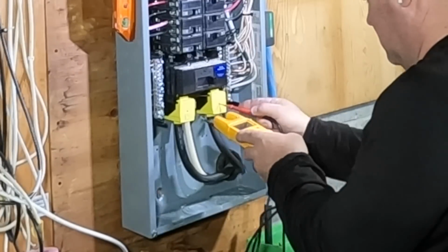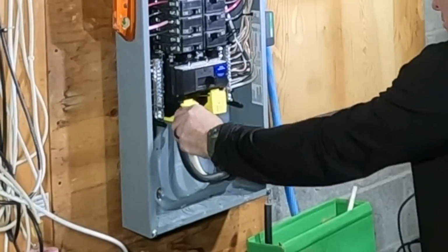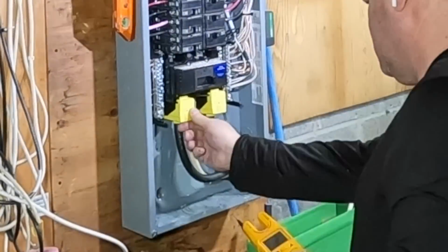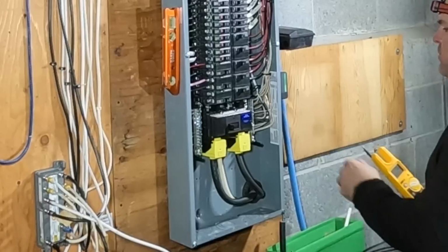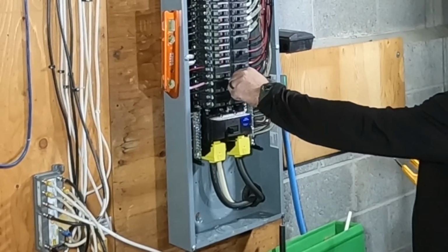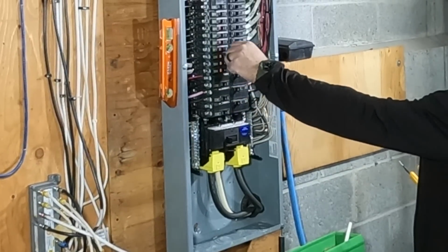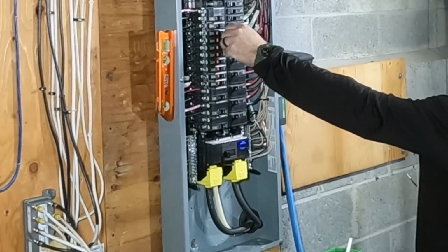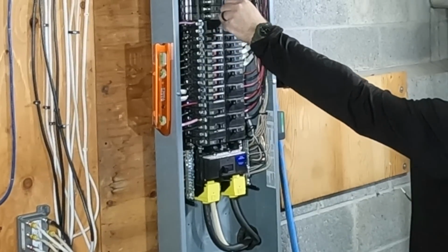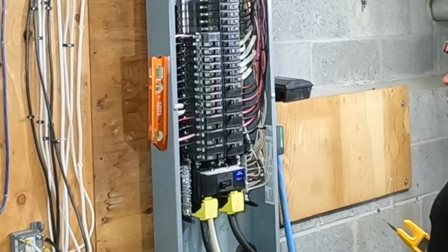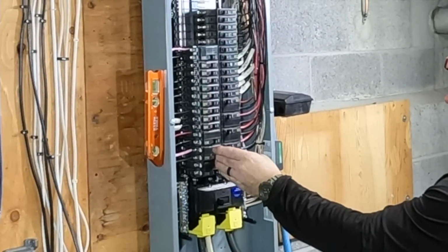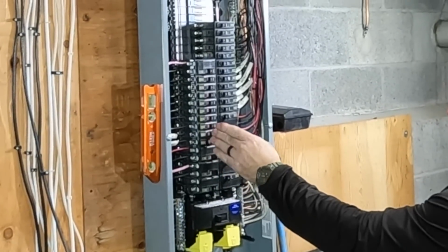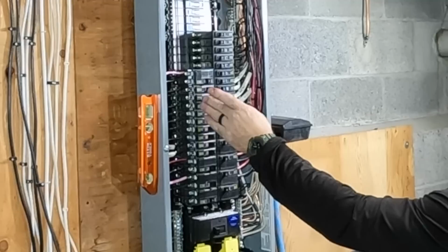Always leave the main breaker in the off position, test for voltage, and then stand away as you turn the main circuit breaker on. Turn on the individual circuits one at a time, and you should be in business. Then I always go back and I check each individual branch circuit to make sure it's working just right. So this is part one of this upgrade, and part two will be coming up shortly once I finish it. That'll include the portable generator wiring portion.